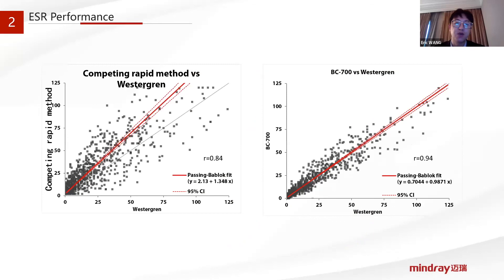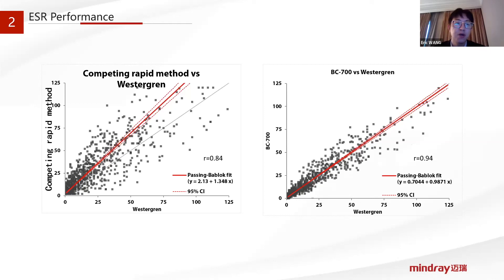We have worked with several hospitals to evaluate the true testing performance of our BC700 series in study departments, including rheumatology and hematology, involving around 300 disease cases. The clinical studies show that the correlation of ESR values from our BC700 series with those from the traditional Westergren method is higher than 0.9, which is much better compared with other rapid ESR analyzers on the market. We also conducted some evaluation in India and will show more data later on.